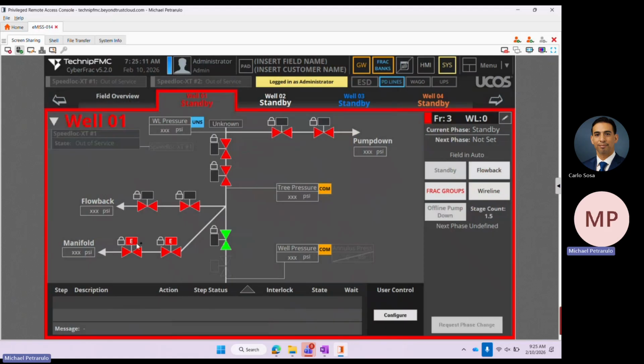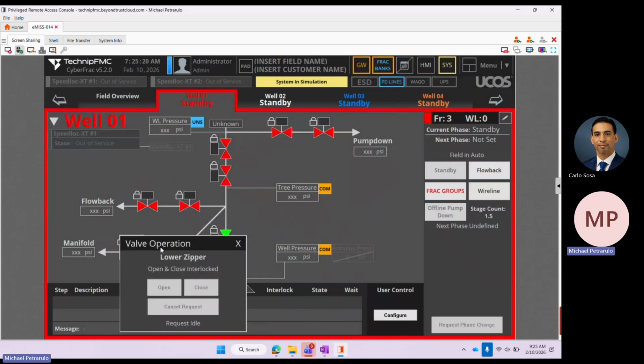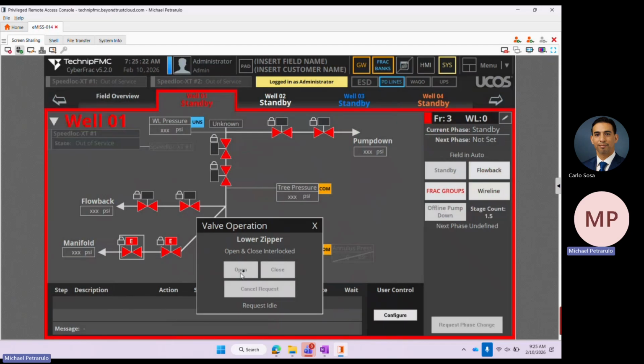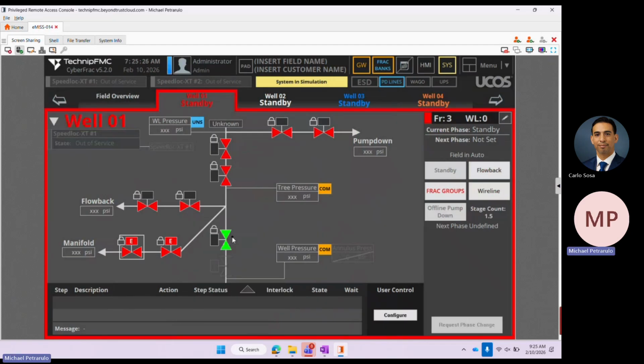You'll notice these little locks show up on the left side of all these valves. These locks mean your valve is interlocked. If there's no letter inside the lock, you're neither allowed to open nor close. If there's an O, you're interlocked from opening, but you are allowed to close the valve. If there's a C, you're not allowed to close, but you are allowed to open.